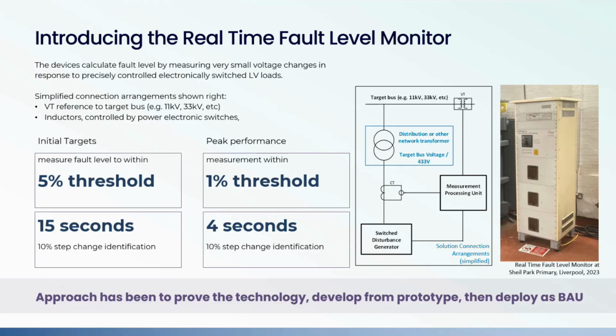So next, let's introduce what the real-time fault level monitor actually is and what it looks like, how we connect it up, and how it operates. You can see on the photograph on the right-hand side of the slide what one of our devices looks like within one of our primary substations. To give an idea of scale, it's a similar size to a standing fridge freezer, or for more technically minded people, a 19-inch comms rack, or just to the left of the photo, you can see it's situated next to a 500 kVA distribution transformer.